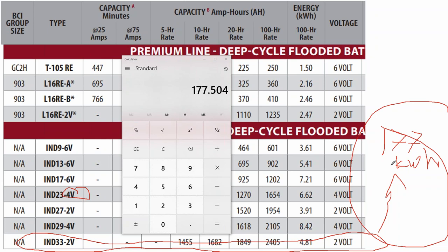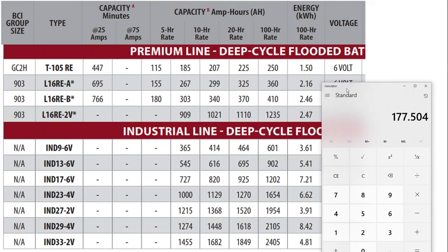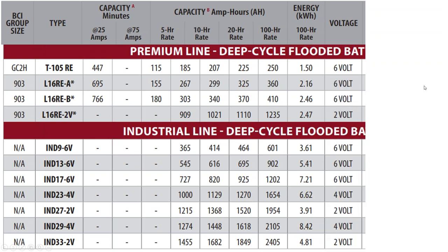And so that's, when you're doing luxury homes, if my home was twice the size of the home for this doctor, and I needed twice the batteries, I'm not even sure I would have been able to find a battery that would have fit within this 2-circuit configuration. I might have had to start dividing up my electrical systems or selecting, say, a different inverter that supported microgrid formation. So I could have a solar array and a battery bank over there and a solar array and battery bank over there. I would only say that SMA, out of the non-commercial, non-industrial battery inverters, really supports microgrid formation right now.